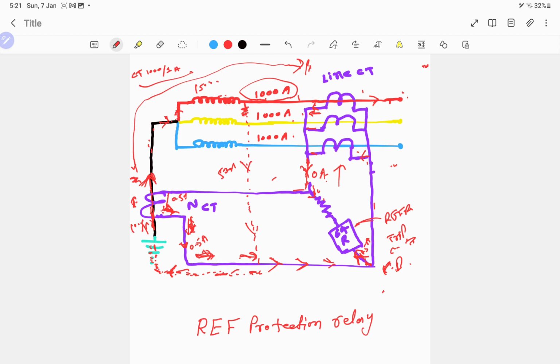But this REF relay will only protect the internal zone of the transformer. It will not help with the external zone of the transformer. So this is the concept of the REF protection relay.